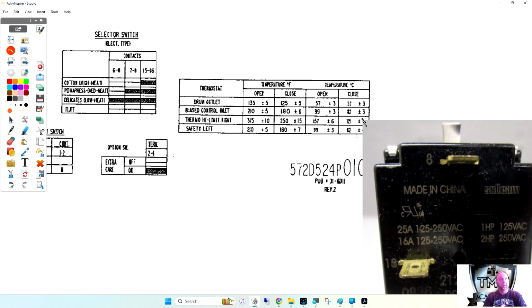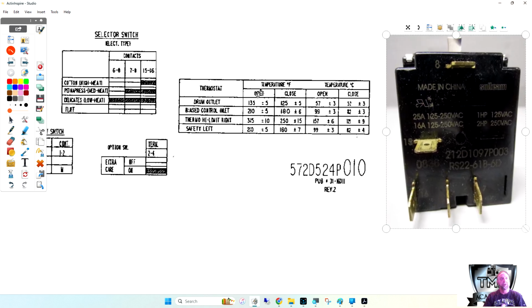Now the other information here gives you temperatures at the outlet of the drum, right where it goes into the blower fan. We've got a thermostat that runs at about 135 degrees plus or minus 5 — it opens at that temperature and closes back at 125, keeping an average of 130 degrees. The biased control inlet, which I'll talk about in a minute, runs at about 210 degrees. The thermal high limit is 315, and the safety is 210. The bottom two are usually not resettable — those are high limits or safeties that, if they go bad, just open up and don't work anymore.